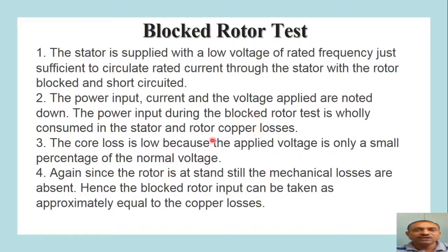The power taken during this test will be utilized to feed only the stator and rotor copper losses. As we are applying a low voltage in this test, the core losses will be very small, so we can neglect them as the applied voltage is a very small percentage of normal voltage.